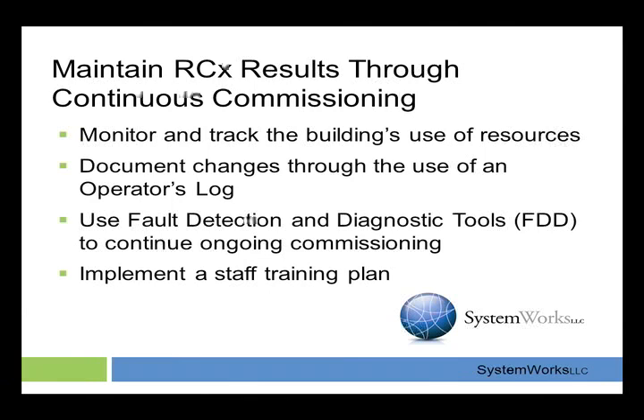Fault detection and diagnostic tools are really something we've been doing, since these automation systems are so powerful. They can be programmed to run a summary on a monthly basis of your variable air volume boxes. They can do a reheat summary and identify issues, simultaneously heating and cooling, and airflow issues.